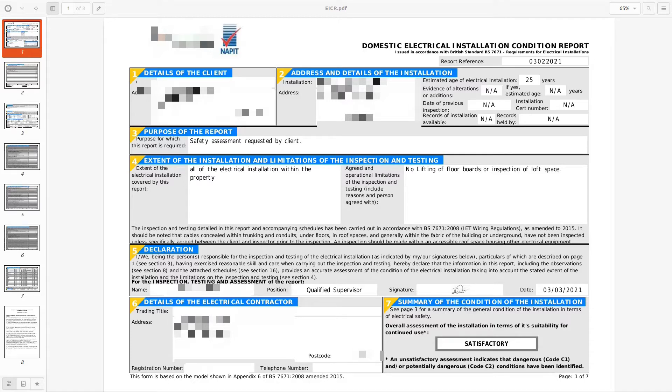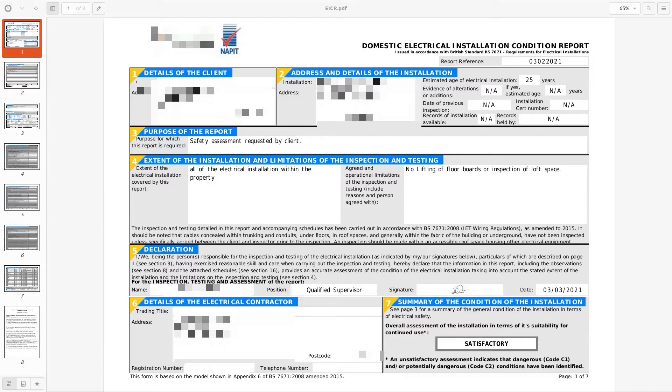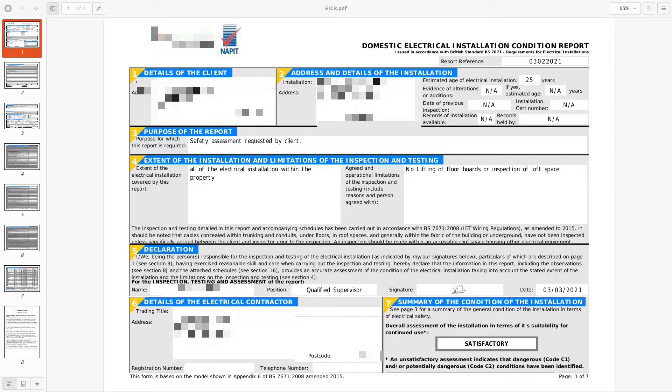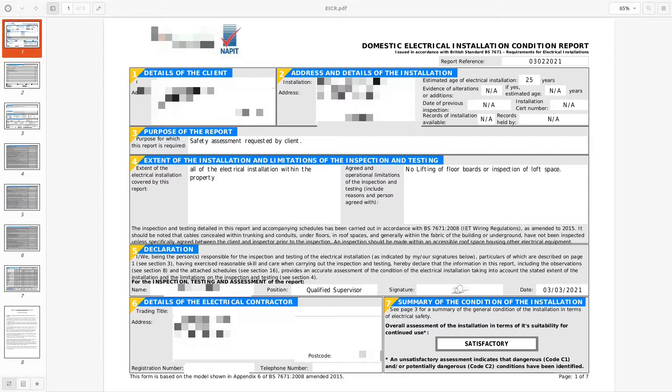The extent: the installation covers the electrical installation and they have agreed that there are no floorboards to be lifted or inspection of a loft space, which is a little bit I certainly frown upon. Anyway, there's no reason why you can't look in loft space unless it's completely inaccessible. We tend to find sockets coming off lighting circuits and all sorts of an array of junction boxes with no lids on and also cobbled together.